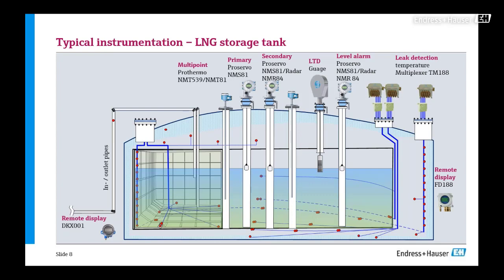The next one is the leak detection, which is a skin point temperature combined with a multiplexer. This skin point temperature is installed outside the inner tank - between the inner tank and the outer tank, you have this multi-point temperature installed at the bottom of your tank. The multiplexer collects all the RTD elements, and from the multiplexer it gives an output going to your system. Depending on the number of elements, it corresponds to the number of multiplexers - one multiplexer can accommodate up to 16 inputs, so if you have 32 or more, you just need to multiply the number of multiplexers.